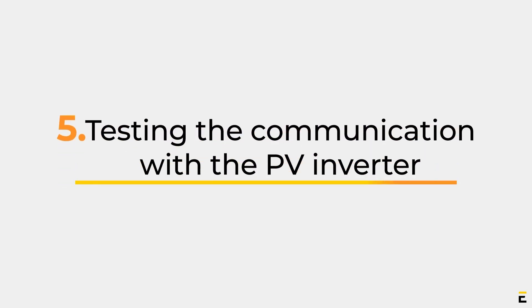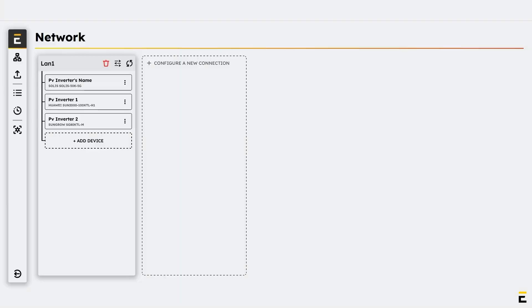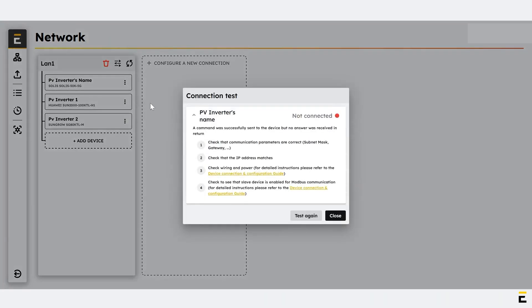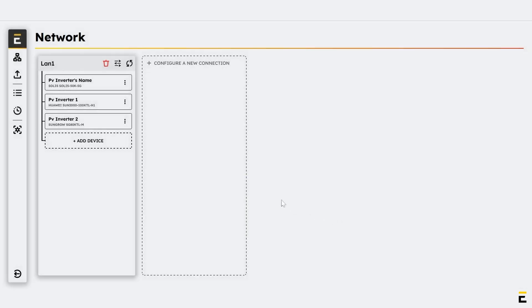Part 5: Testing the communication with the PV Inverter. To test the connection between Ellum's device and the PV Inverter, first check the communication status by clicking on the three dots next to the name of the PV Inverter you added. Click on Test. If your PV Inverter is not connected, this window will appear with the not connected red indicator. Follow the provided troubleshooting instructions to help resolve the communication issues.